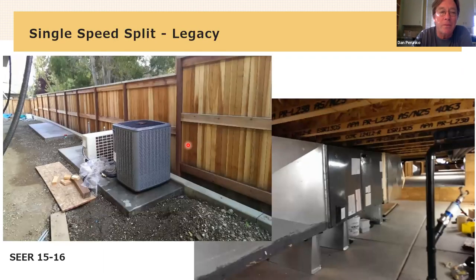All right, so this is a single speed legacy unit, right? Like, again, it just kind of looks like a cube in the yard. It might have 1 speed, it might have 2 speeds, but it's basically those on-off circuits. And its efficiency tops out at about SEER 16. SEER is a rating in BTUs per watt under a test condition used to rate air conditioners in particular.